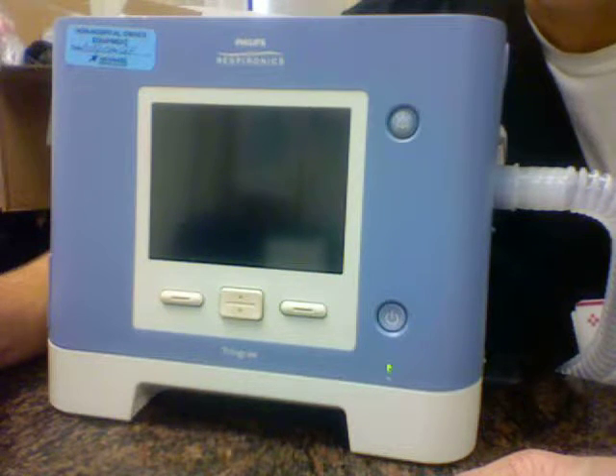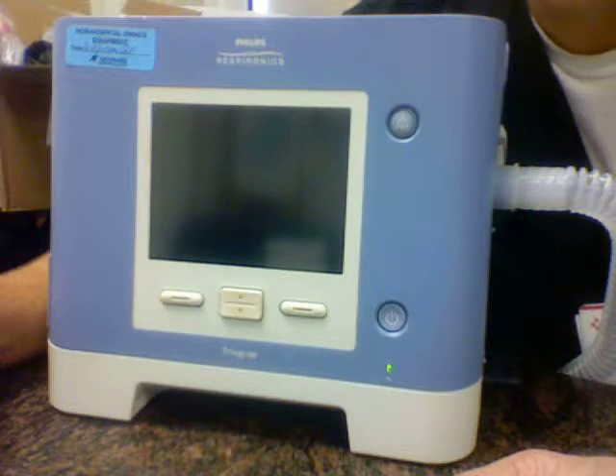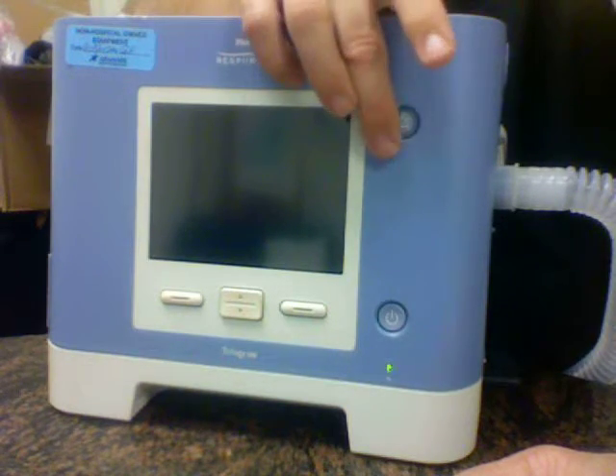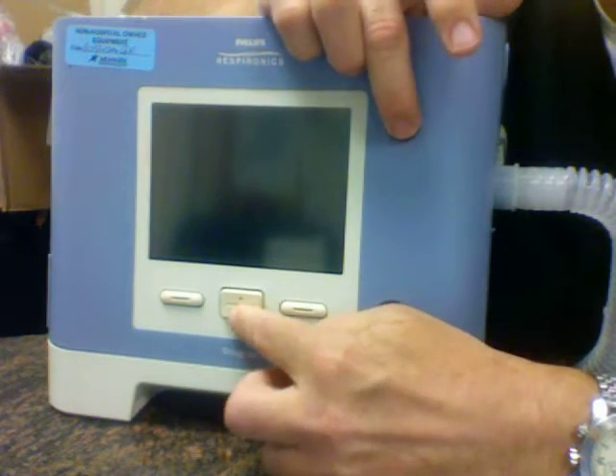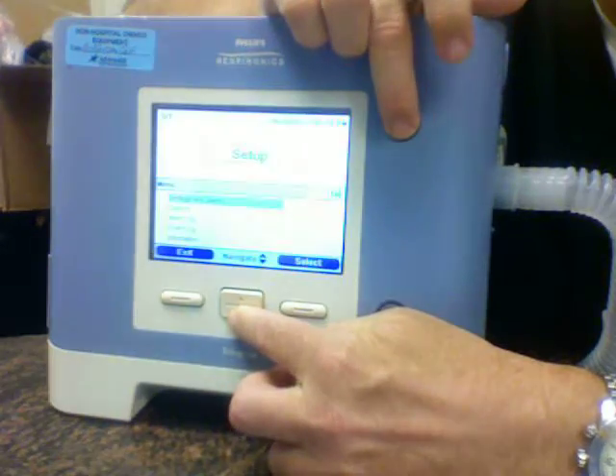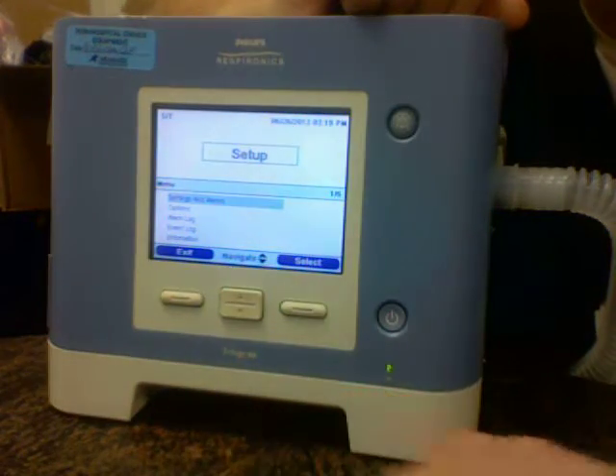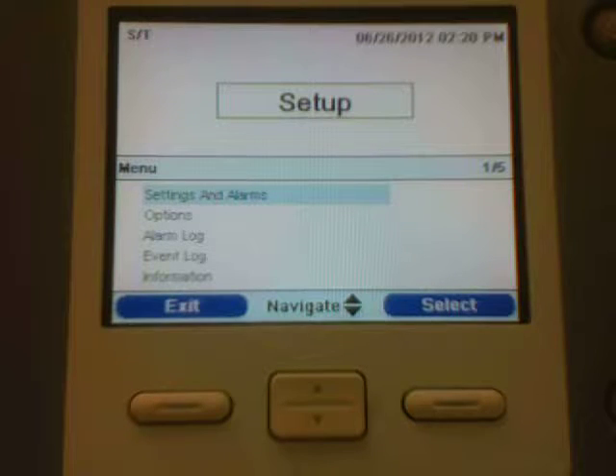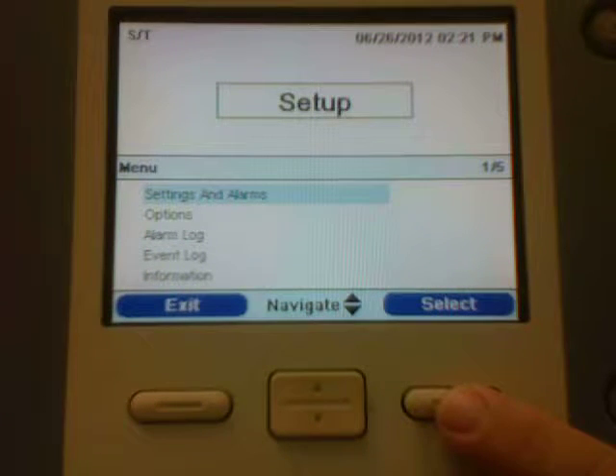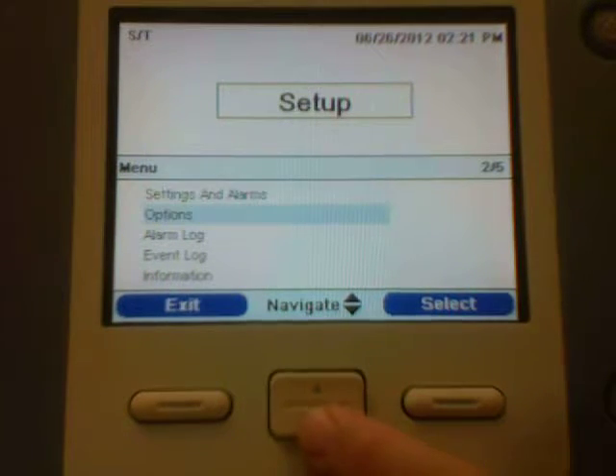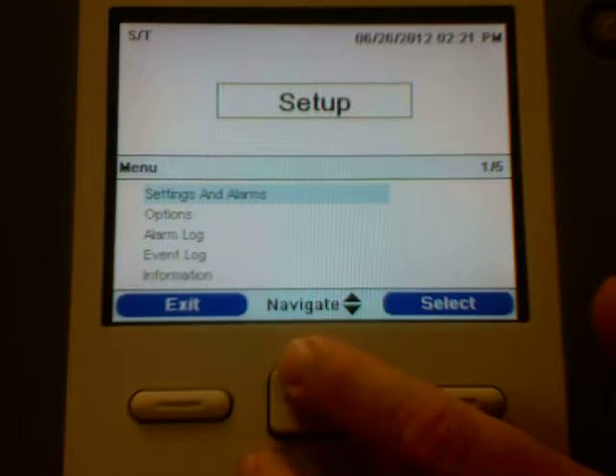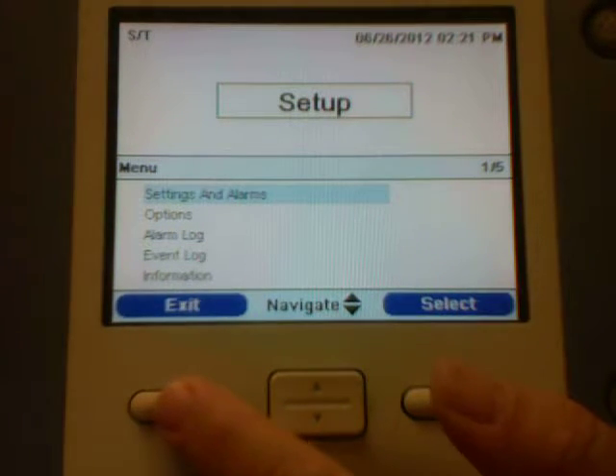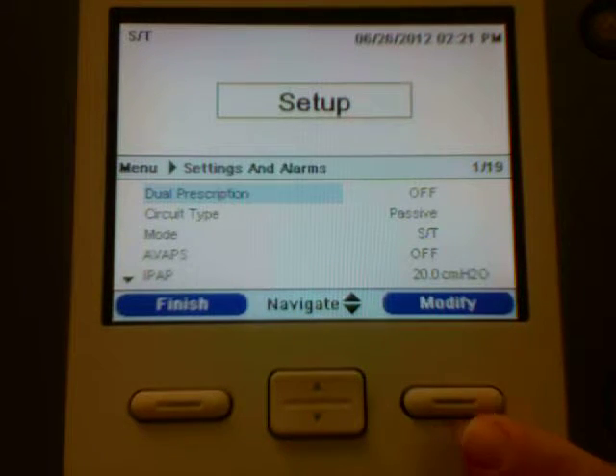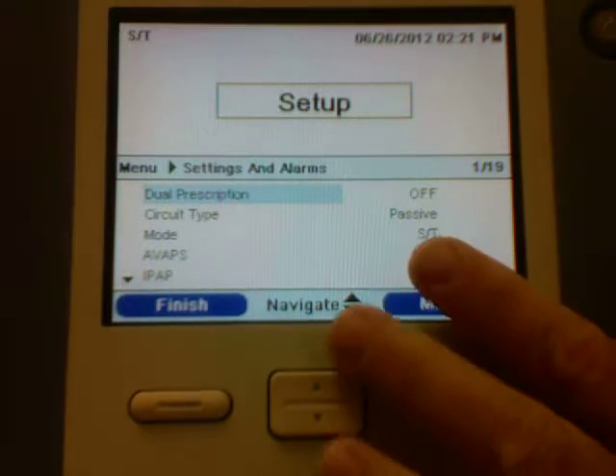Okay, the first step in getting started is to get into the secret clinical setup menu, and you do that by hitting this alarm silence button and the down arrow. Push them together and you get into the setup menu. From that menu, you can see that we have some soft keys on the bottom here, and I'm going to hit Select under Settings and Alarms. I could scroll down and go to different items on this menu, but I want to start out here, so let me hit Select. Okay, now we see several options.